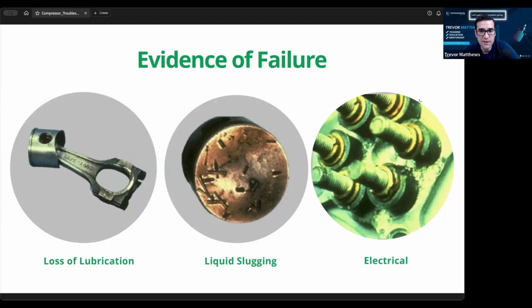And also, if you see the terminal lugs and they're all rusted and damaged, cut the wire and put new lugs on there. It comes in the kits. Put them on there, because I've seen time and time again where a compressor failed because they just used the old wiring. That was the issue the whole time. It was loose and you could not tighten that lug. Correct.